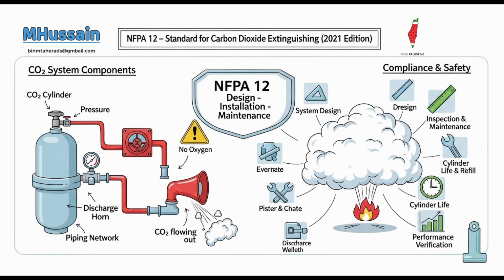When it comes to alarms and delayed discharge, the system is designed to provide alarms within the protected area immediately upon fire detection. Immediate warning inside. This is carefully synchronized with a delayed CO2 discharge and automatic door closures, allowing personnel sufficient time to evacuate before the gas is released. Time delay is key. Crucially, continuous alarms must sound at the entrances to these areas until the atmosphere is restored to normal and verified safe for entry. Alarms outside, too, until it's safe.